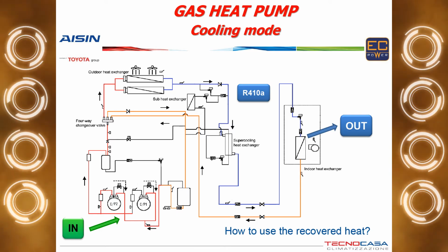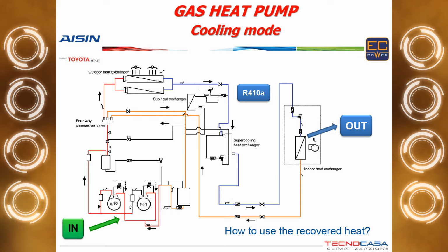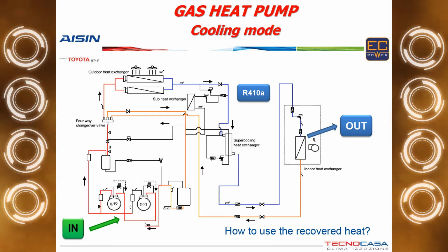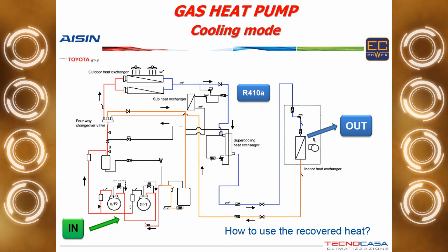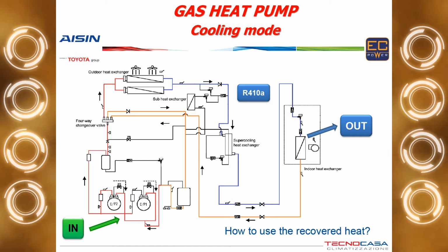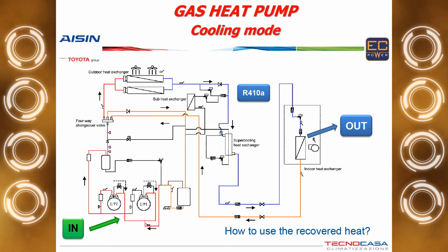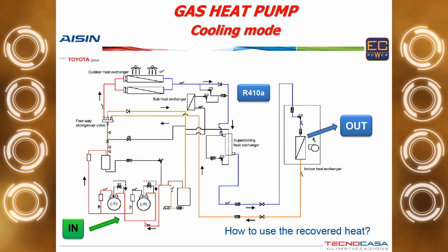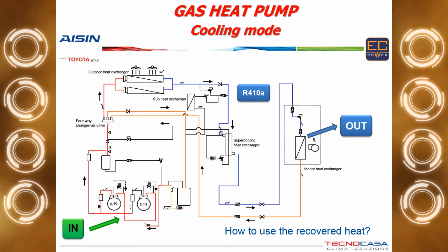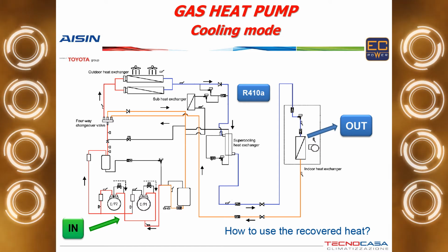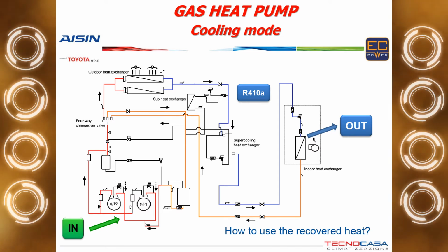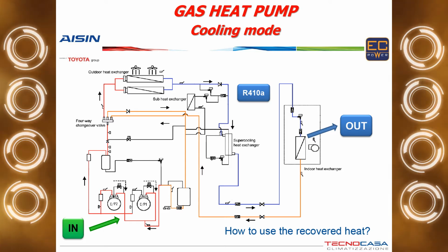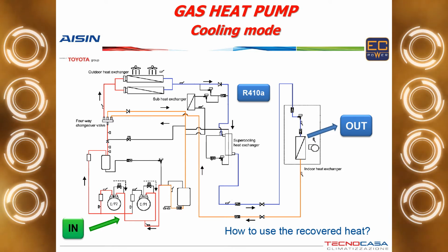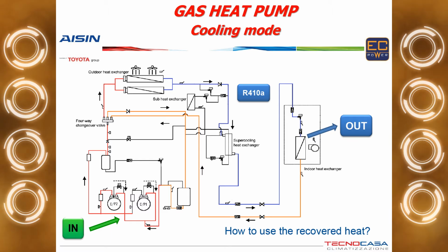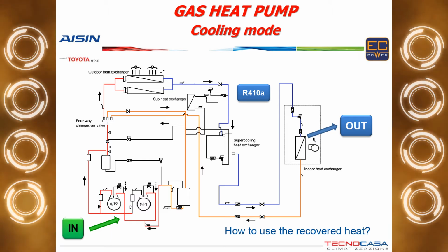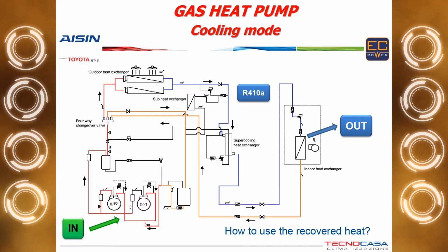In cooling mode, we use the air to condense the refrigerant, which is R410A. We have some sensors to monitor the condensation process, and so to change the speed of the fans according to the need of condensing the refrigerant. This allows a reduction of the electricity needed for the heat pump. Then the mixture goes into a supercooling heat exchanger, which is needed because we can reach a very high distance with the indoor units, and we don't want flash evaporation to happen in the pipes.